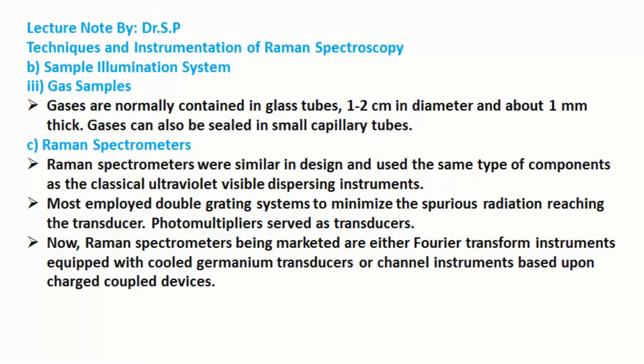Raman spectrometers were similar in design and used the same type of components as classical ultraviolet-visible dispersing instruments. Most employed double grating systems to minimize spurious radiation reaching the transducer, and photomultipliers served as transducers. Now, Raman spectrometers being marketed are either Fourier transform instruments equipped with cooled germanium transducers or channel instruments based upon charge-coupled devices.